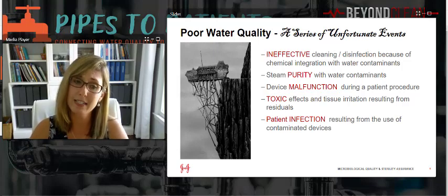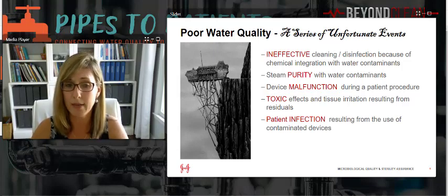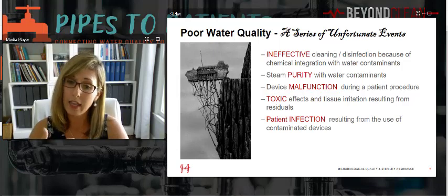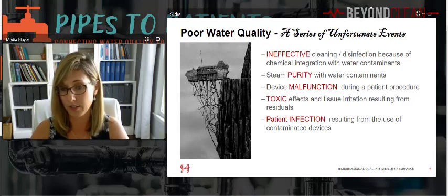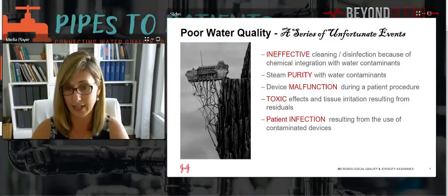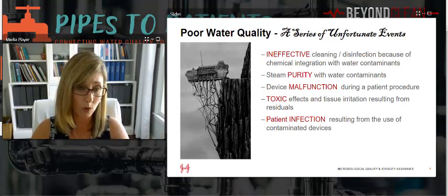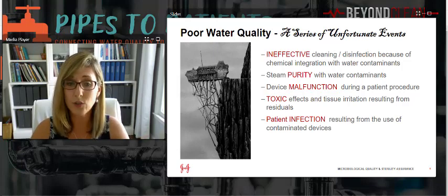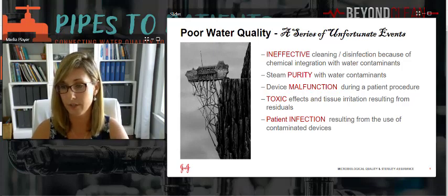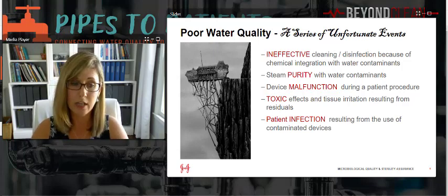So the third one is device malfunction. We really want to make sure that when the device is used on the patient, it performs correctly each and every time. And if water is used on a device and it causes that device to corrode, because maybe it's salt or other water deposits, the device could actually break during that patient use and that mechanical movement. So we want to make sure that any kind of water exposed to the device is not going to cause the device to malfunction prematurely.